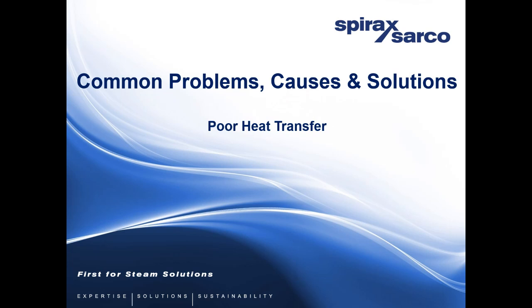That's well put. So I'll go to the next question. How can we quantify the loss of energy in the flash system? So if you're talking about flash steam, you're losing. If you know your incoming pressure, then the pressure downstream. Say we're going into a condensate recovery unit, which is then normally at atmospheric pressure. You have a steam line or a condensate line, which is discharging into there at 3 bar. You know the differential pressure there, so you can calculate the flash off, therefore the energy lost in your system.